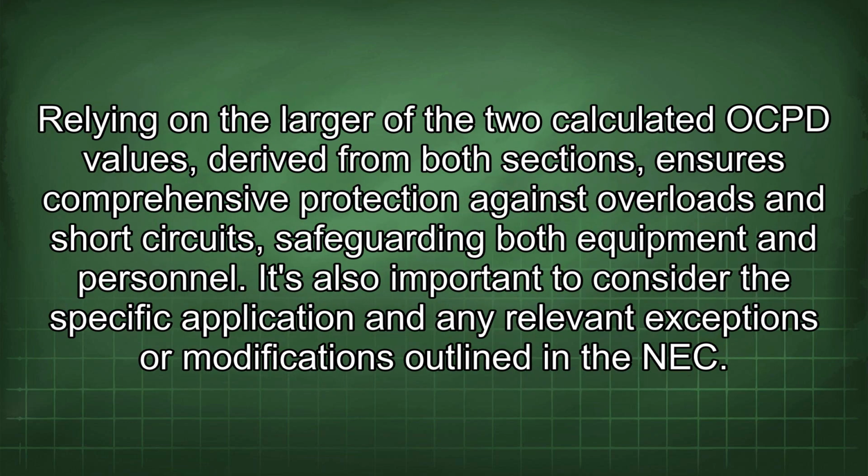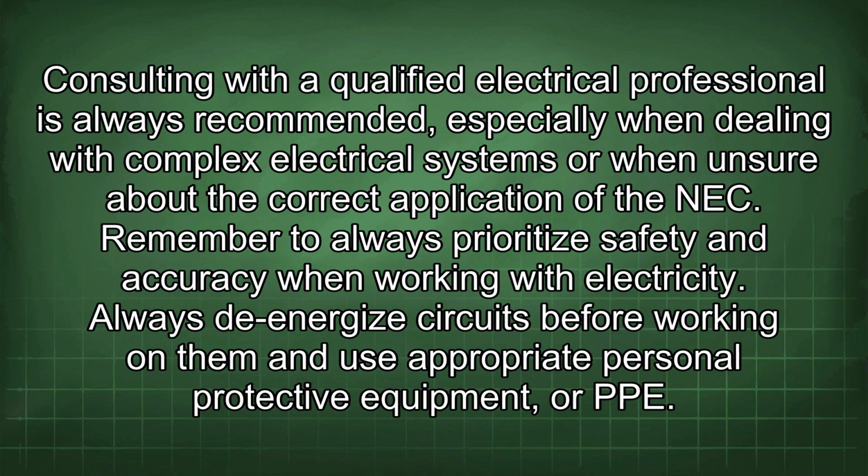Relying on the larger of the two calculated OCPD values, derived from both sections, ensures comprehensive protection against overloads and short circuits, safeguarding both equipment and personnel. It's also important to consider the specific application and any relevant exceptions or modifications outlined in the NEC. Consulting with a qualified electrical professional is always recommended, especially when dealing with complex electrical systems or when unsure about the correct application of the NEC.